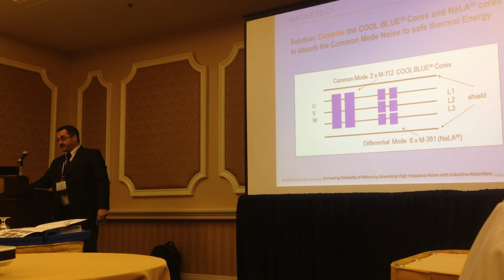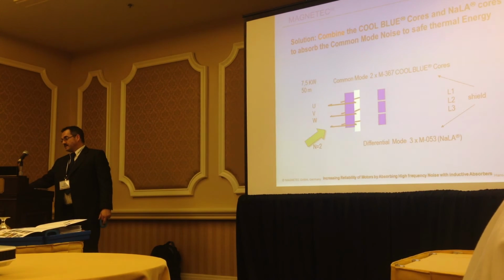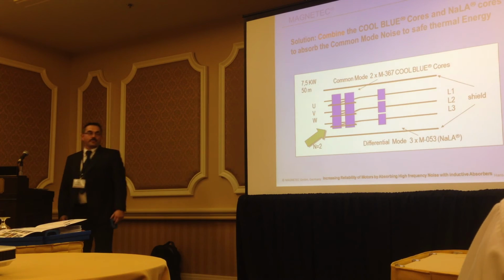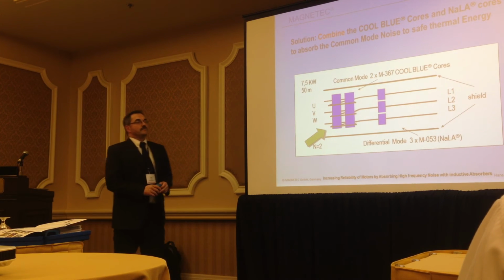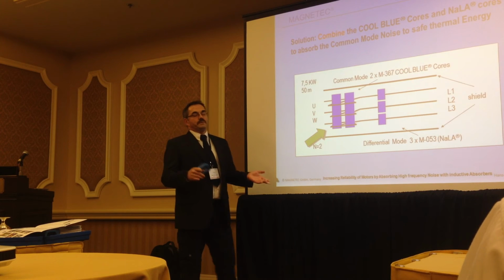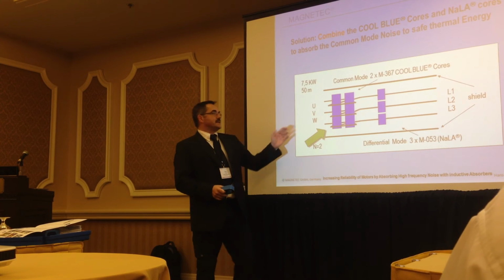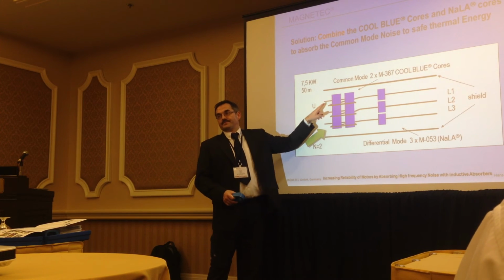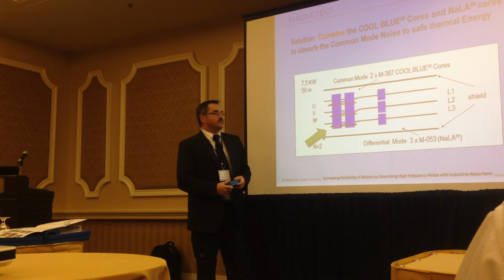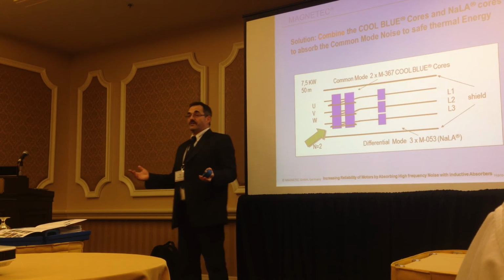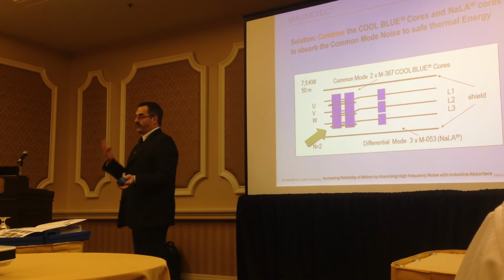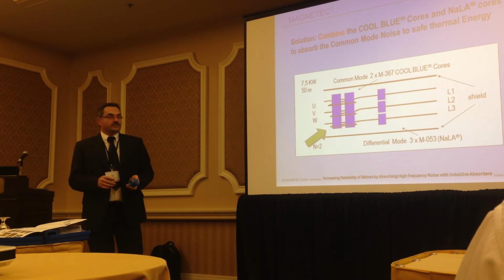If you are in the lower power range, there's a trick which helps save you money - something like this. To reduce the amount of cores, especially when you go maybe 10 horsepower or less, it's allowed to use more turns. That means if you have 2 turns, you do not have double the noise suppression, you have a factor of 4.